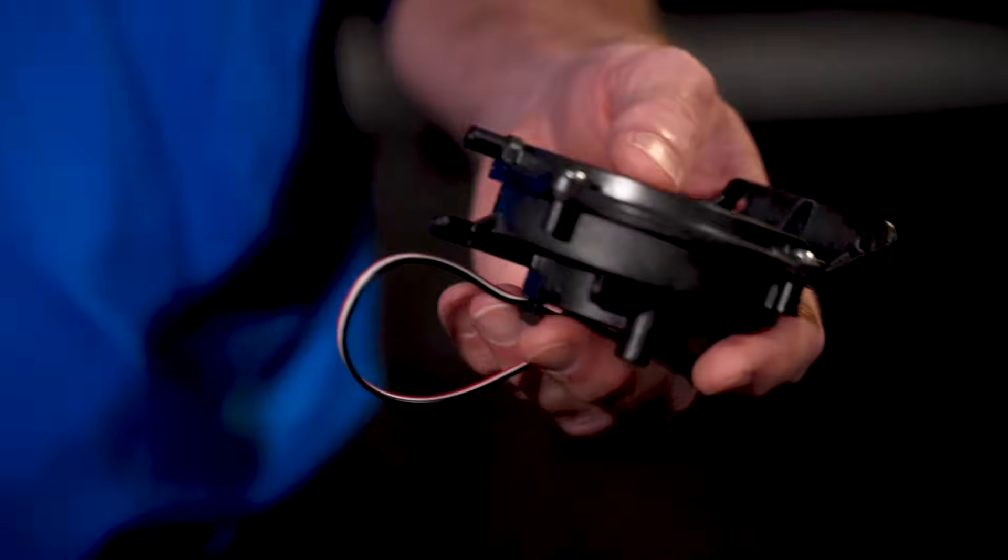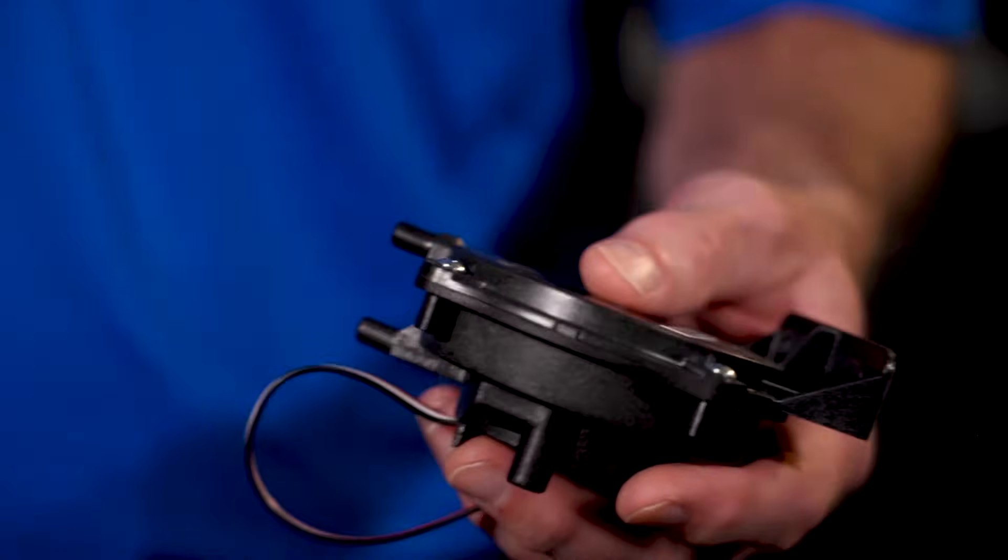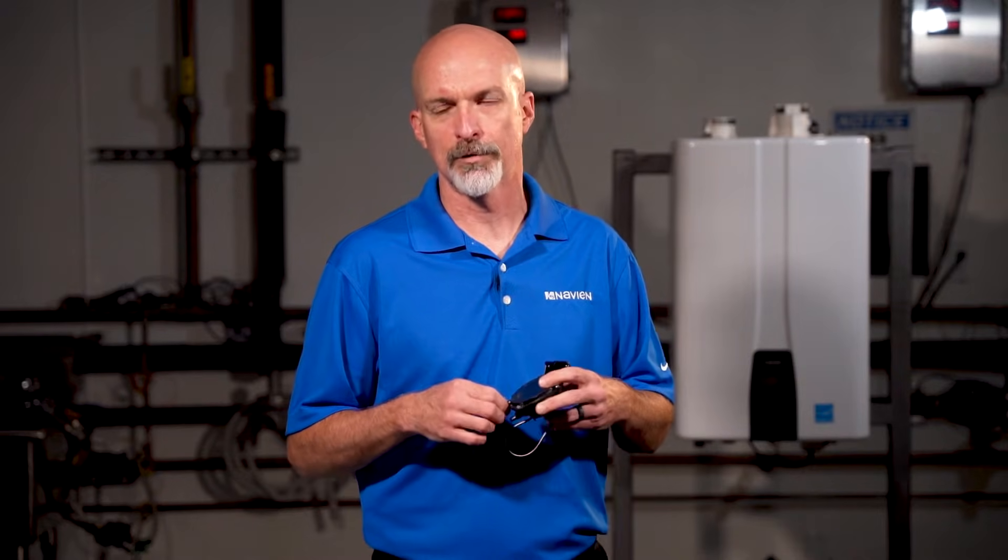Inside our combis, water heaters, and boilers also is an air pressure sensor. The air pressure sensor will monitor and periodically check the vent pressures for both the exhaust and intake. This will also detect a vent blockage, preventing unsafe operation in the unit.